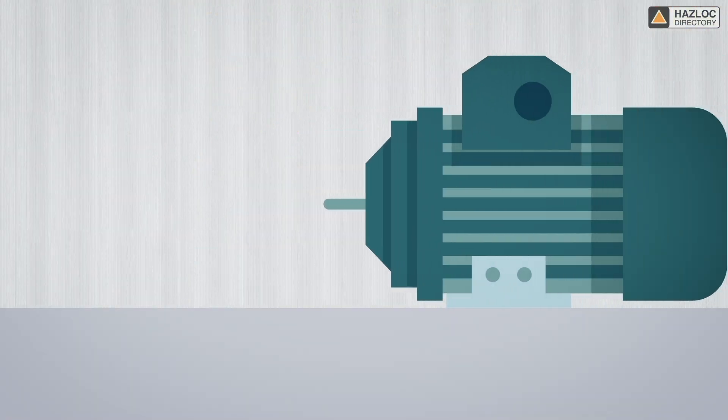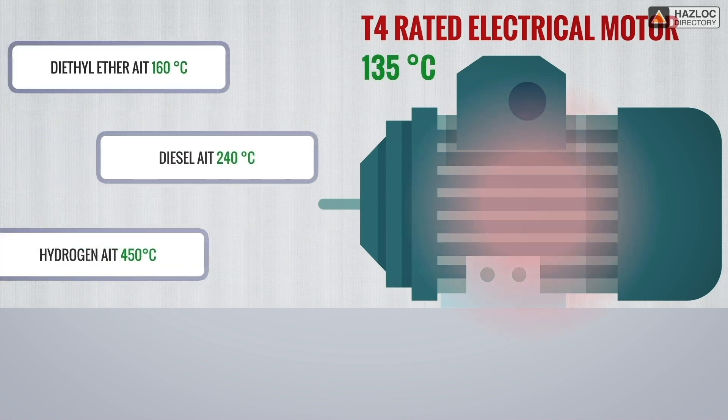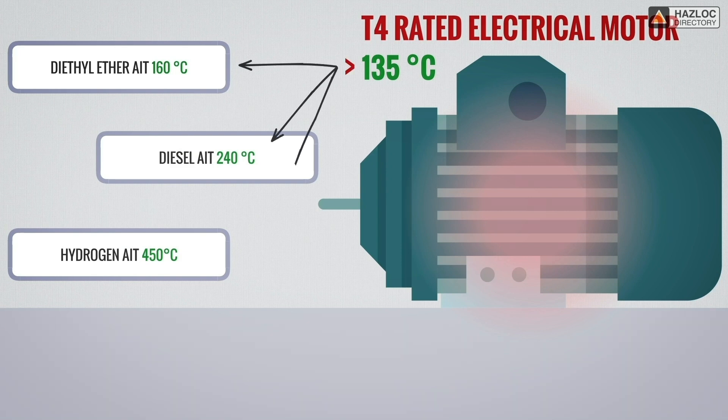Now this T4-rated electrical motor can be safely installed in an area when diethyl ether, diesel, or hydrogen are present because the minimum ignition temperature of these gases is higher than maximum surface temperature rise of our T4 motor.